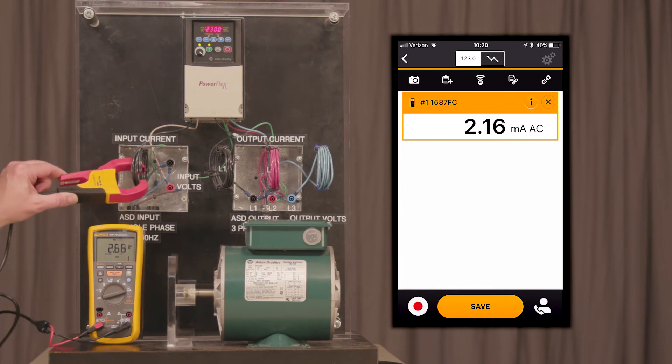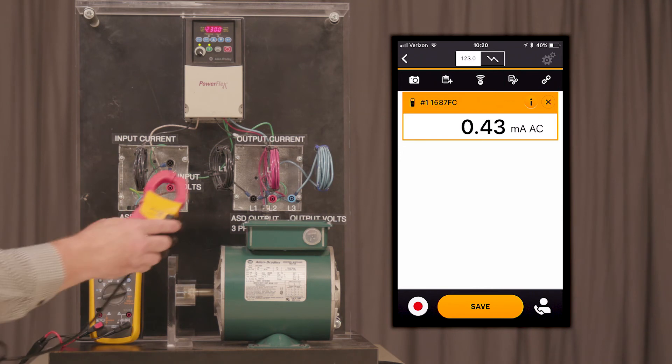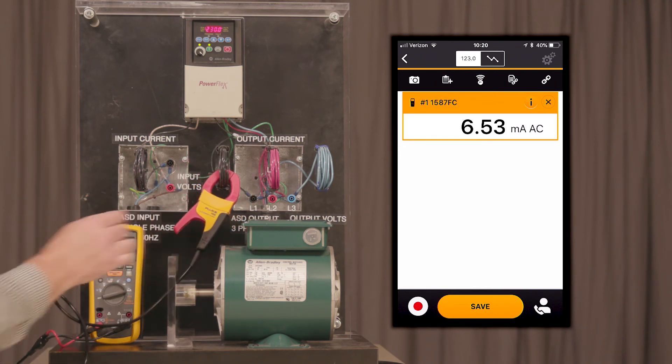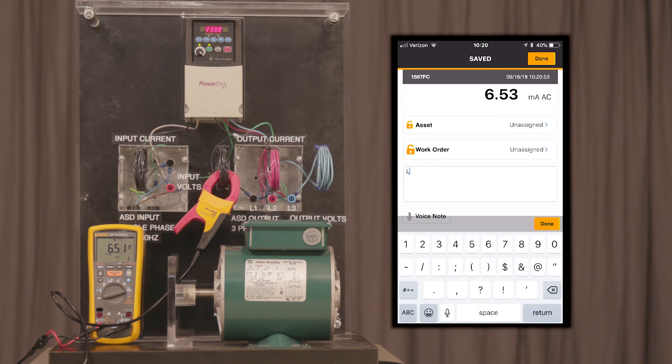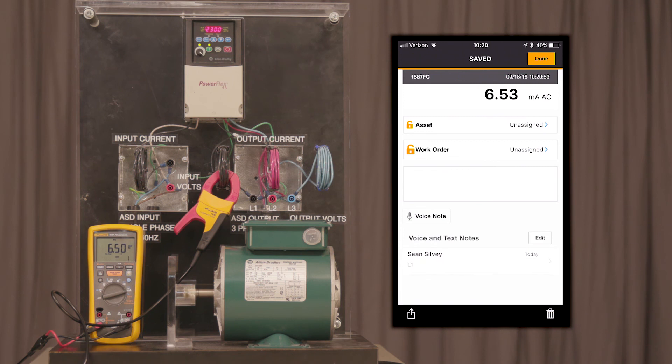Let's go ahead and now make a measurement on the output of the VFD for L1, L2, and L3. We're going to go ahead and save this measurement for L1, 6.5 amps. You will repeat this for all three phases.